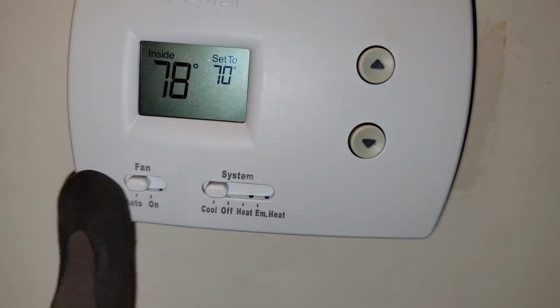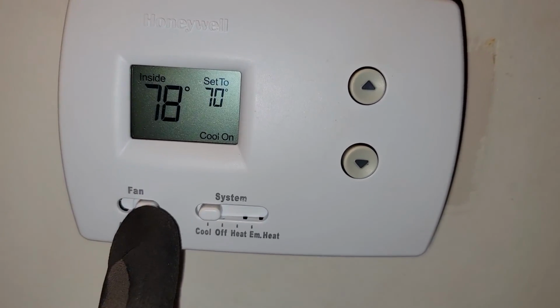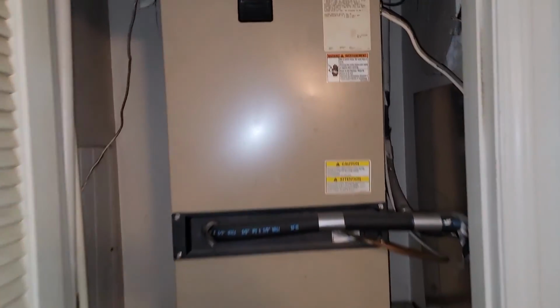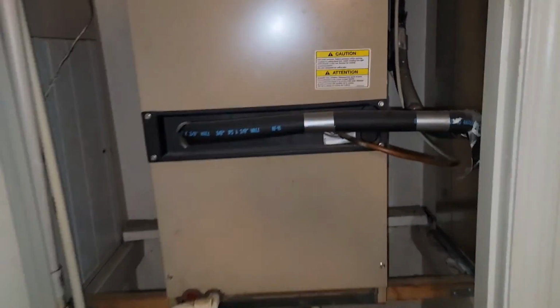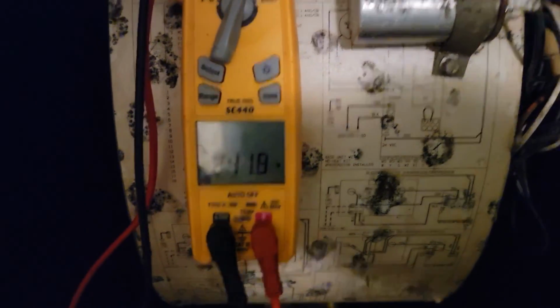Unit set on cooling. Turn the fan on. Doesn't do anything. There's the air handler. Let's open it up, see what's going on. All right, we got 241 volts. Checking the main power coming in.